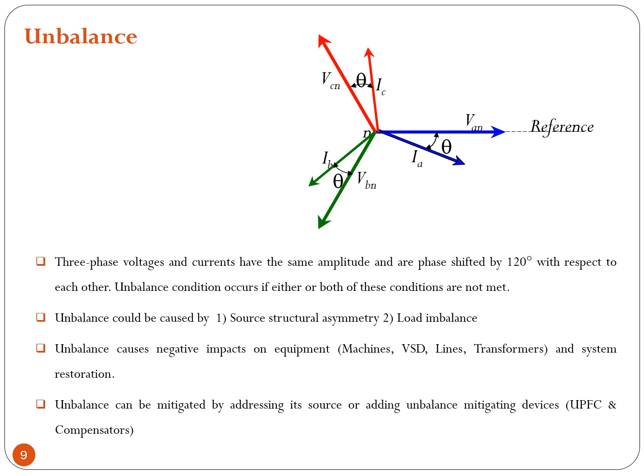Voltage balance means the three-phase voltages and currents have the same amplitude and are phase shifted by 120 degrees with respect to each other. An unbalanced condition occurs if either or both of these conditions are not met. Unbalance could be caused by source structural asymmetry or load imbalance. Unbalance has negative impacts on equipment such as machines, variable speed drives, lines, transformers, and causes system distortions. Unbalance can be mitigated by addressing its source or adding an unbalance mitigation device like a Unified Power Flow Controller (UPFC) or compensator.